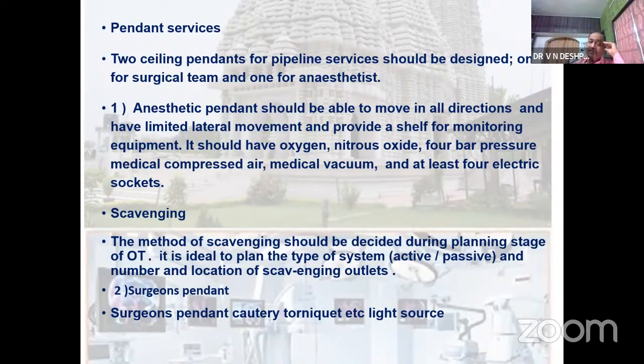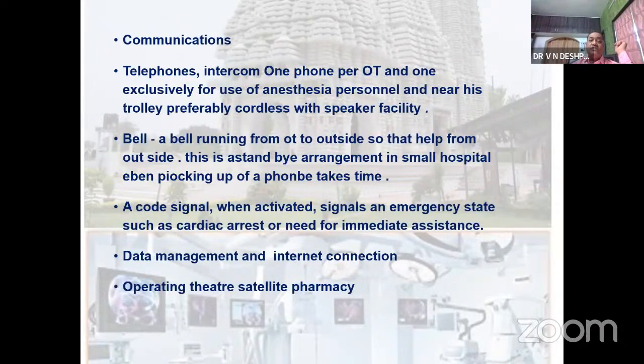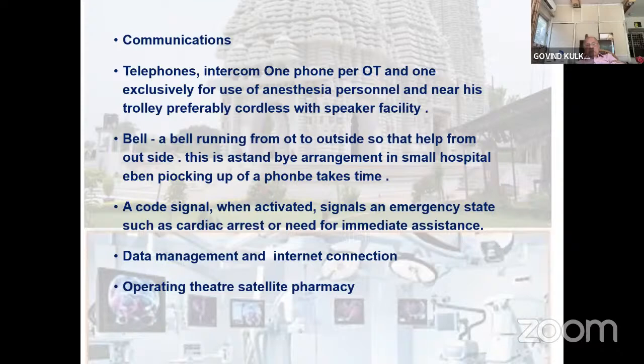The scavenging system, it's exhausting out of the anesthesia gases. This scavenging system is also very important. It's active and passive. Most of the theaters in small hospitals may not have a scavenging system, but it reduces your tiredness, it increases your efficiency. There has to be a communication system, telephones, intercoms, and code signals activated. But I will suggest a bell system, because in a small hospital of 25 or 30 beds, wherein manpower is also less, picking up a phone may also be difficult for the staff sometimes.